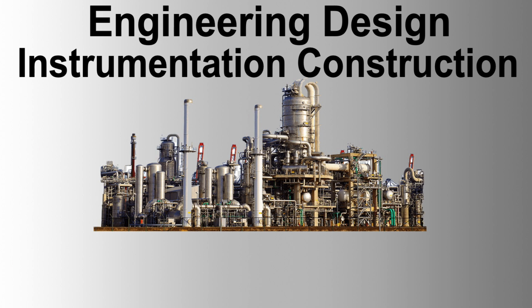For critical applications, the bypass valve shall have the same body and trim construction as the control valve, but with hand wheel operation only. Provisions shall be made for draining and/or depressurizing the control valve manifold. At least one drain valve shall be provided adjacent to the control valve, preferably downstream of the same, depending on the physical layout. But shutoff valves shall always have a drain valve on the downstream side for leak testing the valve. For hazardous, corrosive, or toxic fluids, more extensive provisions may be required. Startup strainers shall be provided upstream of control valves with a labyrinth-type low-noise trim.